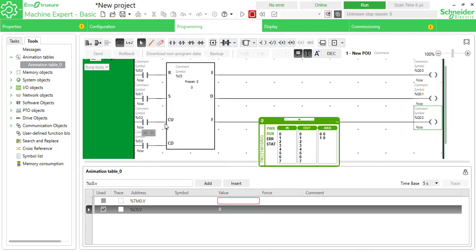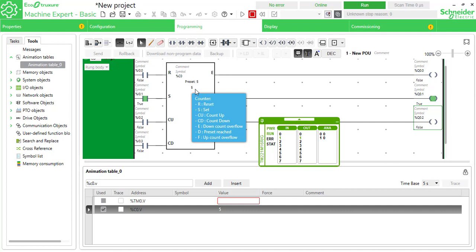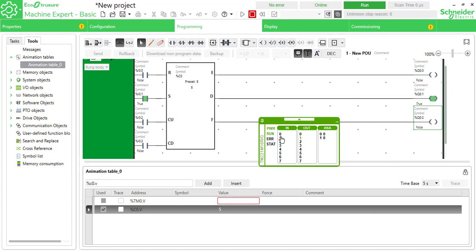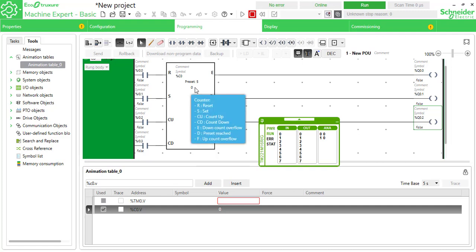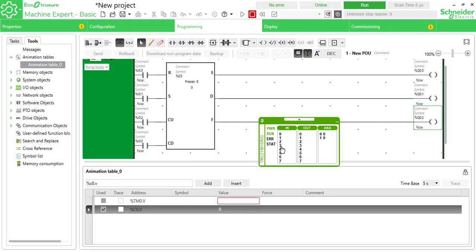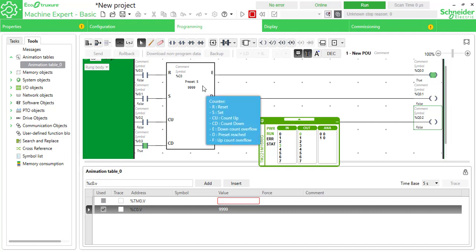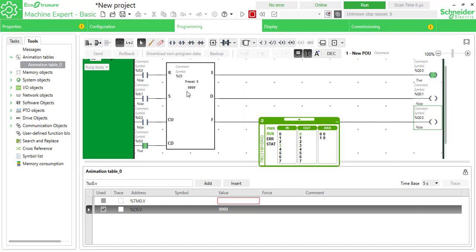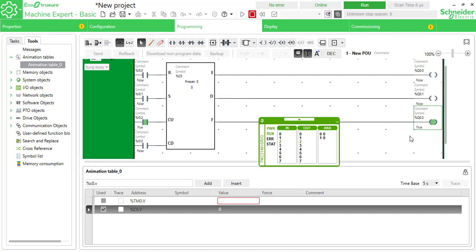The set function sets the accumulator or current value to the preset in a single toggle. Reset it again, then try down counting. Using I0.3 for down counting — down counting from zero gives the down count overflow, reaching 9999. Counting up from 9999 gives the up count overflow.